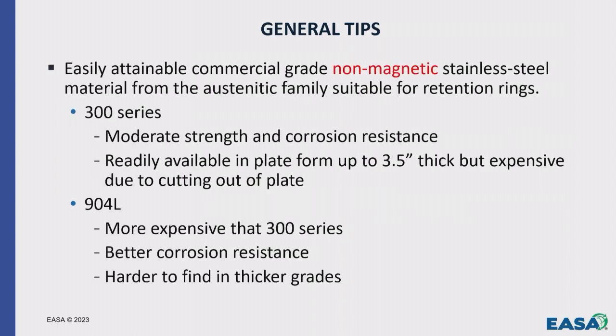So the general tips: the whole main focus of stainless steel rings is they've got to be non-magnetic. Now I'm going to list a few different material types that you can commercially get here in the States for either repair or if you're going to do the conversion. I'm not going to go in depth because I know you guys are repair shops. If you're converting a rotor from aluminum to copper, you're probably going to send it to a rotor repair facility. I don't think too many of y'all are going to do it in your shop. But the whole secret is you have to have non-magnetic steel. If you don't, you're going to generate current in that ring. It's going to heat up, it's going to expand differently, and it's not going to work.